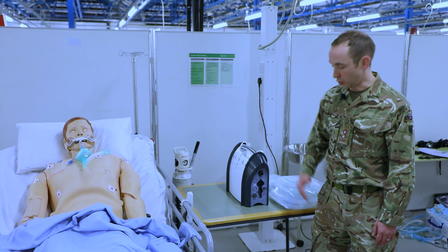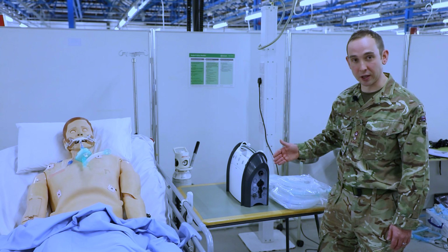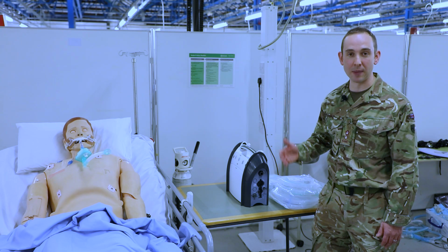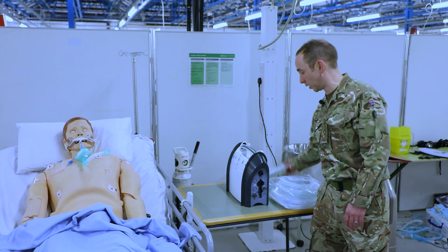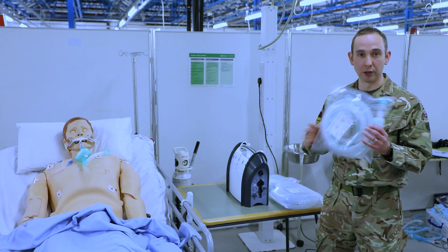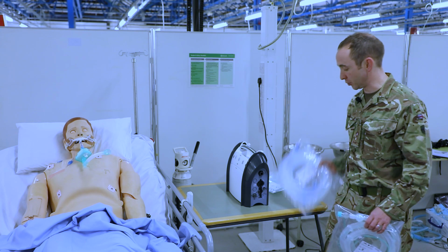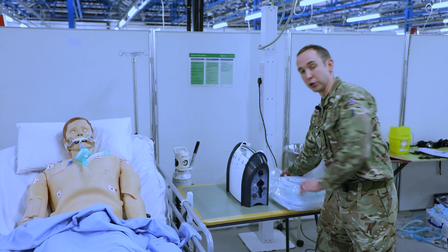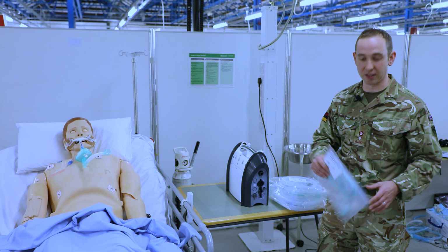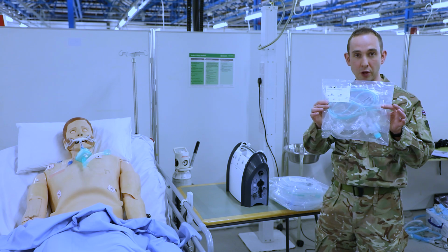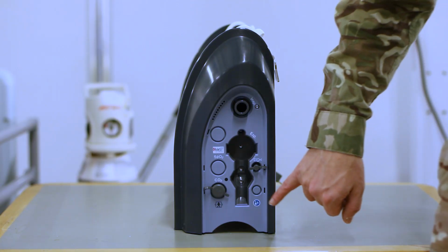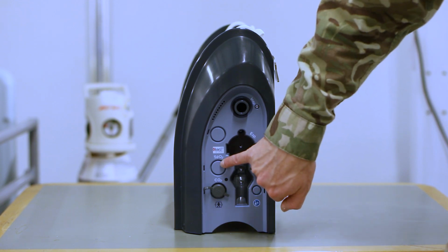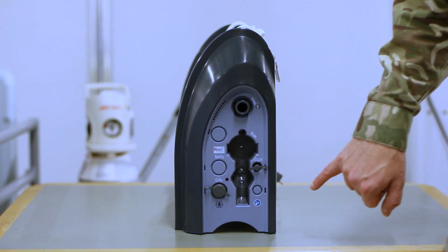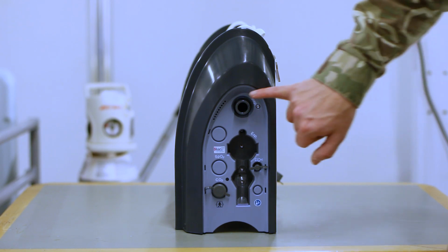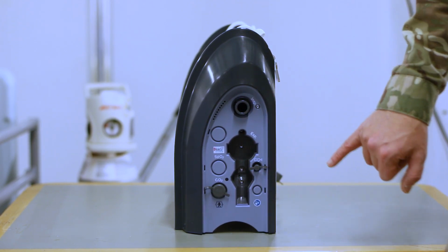So on the opposite side of the Eve is where you connect your circuits. Now currently there are 3 main circuits that we're using, and they come in slightly different packages. We have a single limb circuit, a dual limb circuit, and then if you're using it alongside the DPO2 anaesthetic machine, you'll have a slightly different circuit with no actual circle in there. On this side of the machine, CO2 and SpO2 have not been activated in the defence configuration of this ventilator. There are 3 then ports to allow connections of any of the 3 circuits that are used.